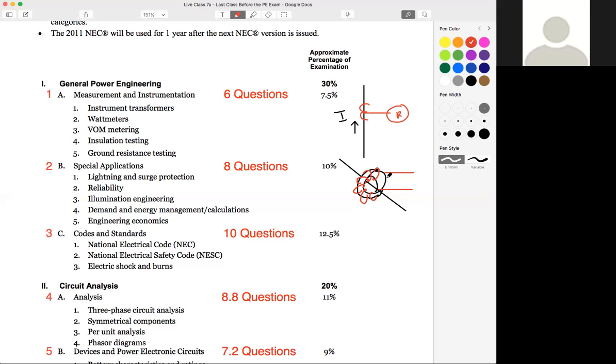So for those of you that aren't sure, if here's our line current, right? We've got a current going here, and our step down current, our secondary, going to our relay equipment, going to our R. If we open these windings, right, what do we have? What is the impedance of an open circuit? That's essentially an infinite impedance, right? And if we look at Ohm's law, where we always start if we're not sure what to do, V is directly proportional to Z. So as soon as we have an infinite impedance, our voltage on that secondary side is going to shoot up, because this current on the primary is inducing, right, a source on the secondary. So it's essentially going to arc between both contacts. That infinite impedance is going to ramp up the secondary voltage so fast that it's going to exceed the impedance of the air gap. And it's going to cause essentially just a really big bang. It's a very big safety hazard.